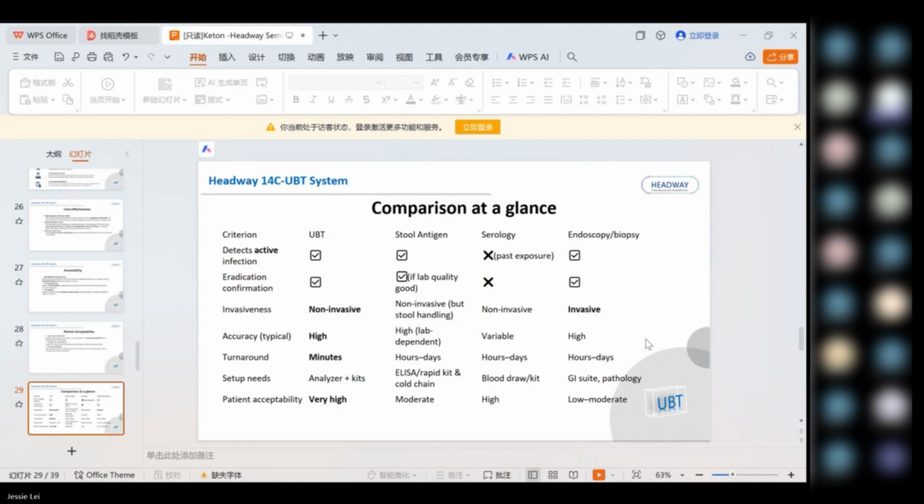Once you have the analyzer in your lab, we do background testing on the initial installation for around 40 minutes. We do the QC checks. We have 2 cards that we do that check with, and you'll be recommended to do the test within a certain duration. You don't need any external reagents or consumables, only that particular card. The cards serve as the calibration point, because we are measuring the carbon released with the kit and also the background. That is very important for us to establish the background of that particular environment.